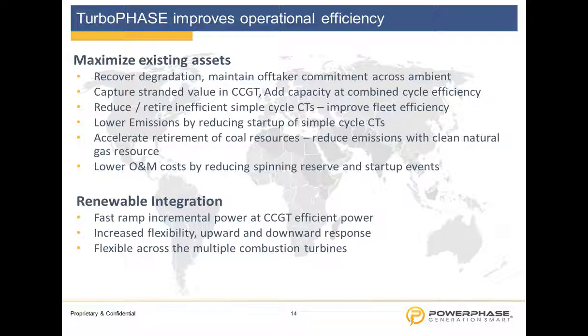And then just to address the operational efficiency, as I talk to different utilities and different, I would say, government-owned grids around the world, there is a unique perspective from the utility point of view, which is to add power to your most efficient assets at combined cycle efficiencies and reduce the inefficient simple cycle CT hours. So if you are going to go put 100 megawatts of Turbophase into the grid, that same 100 megawatts can offset 100 megawatts of simple cycle power. And that 100 megawatts at 55% efficient versus 100 megawatts at 35% efficient is a 20% efficiency change of those kilowatt hours produced. In addition to lowering emissions by reducing startup cycles, and also lowering emissions in tons per MMBTU input because the efficiency improves.